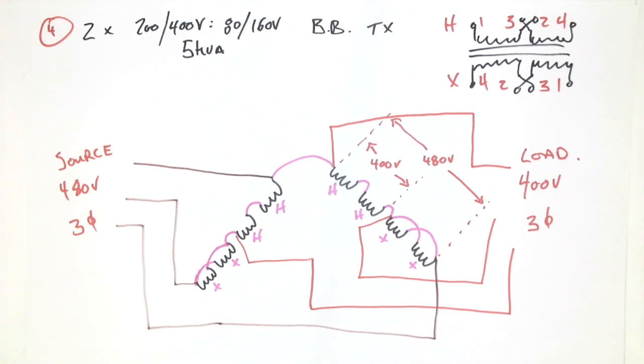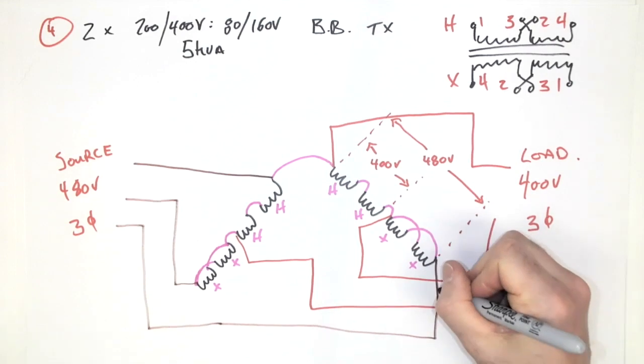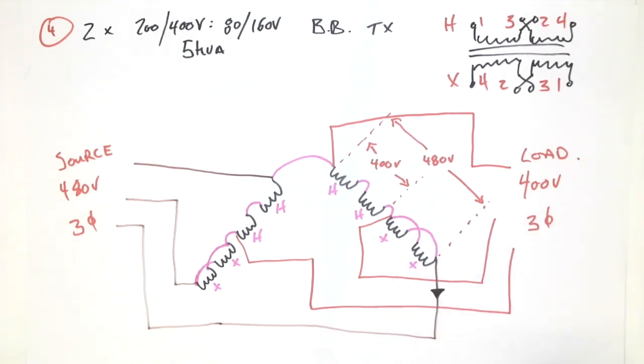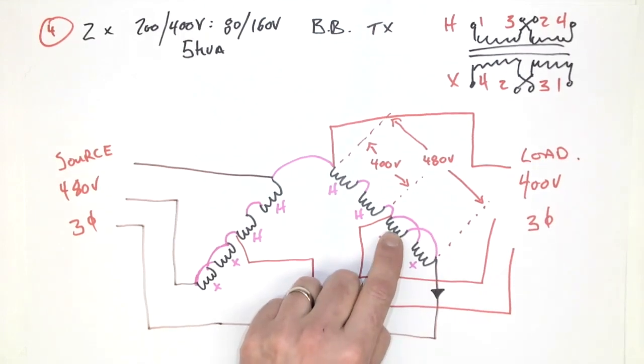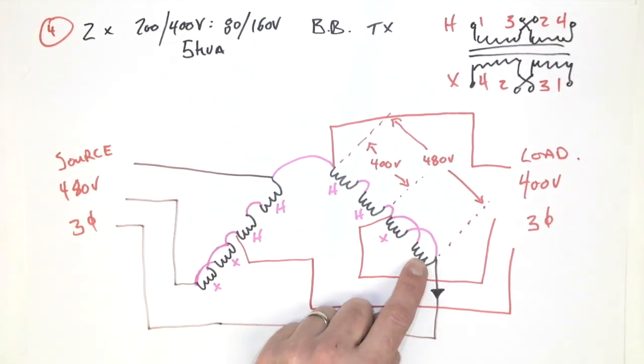Now let's take a look at what we have for a series connection. This one's not as easy for us to identify, but don't worry, it's quite a simple process. So I'm going to look at the end of my open delta connection here. And the open delta connection is actually a parallel connection. What that means is that there's going to be a total amount of current in this location running down this conductor that is equivalent to the current flowing through this winding plus the current flowing through this winding, because they're in parallel. In parallel, the current values add together.